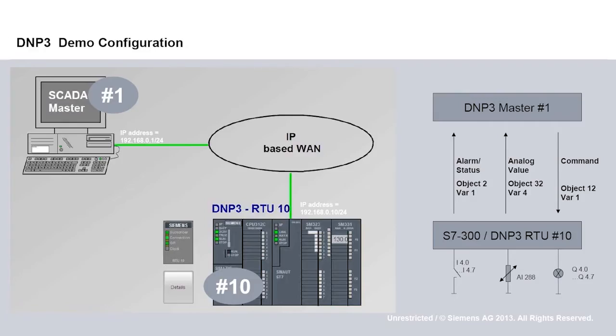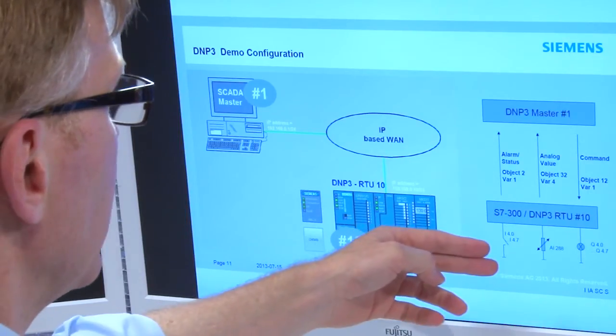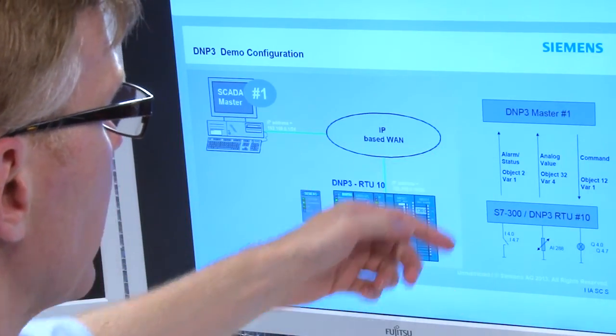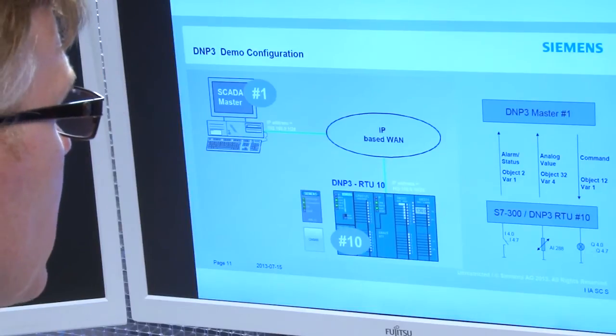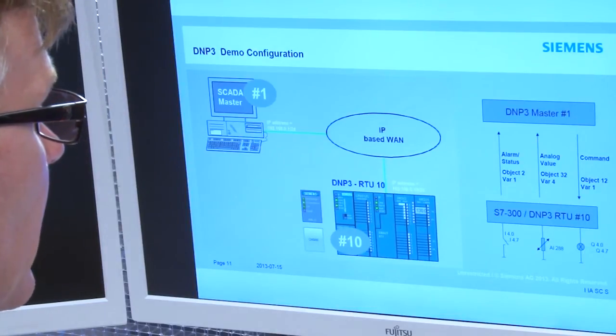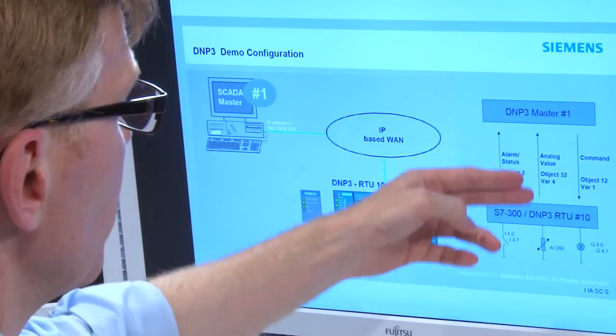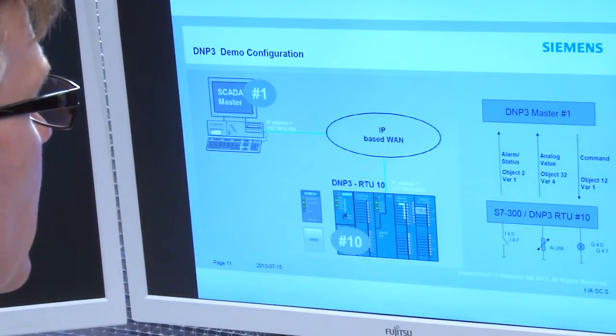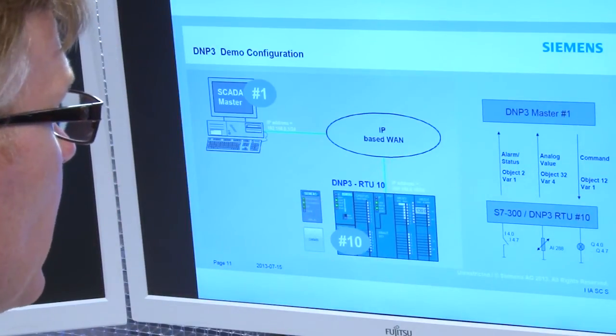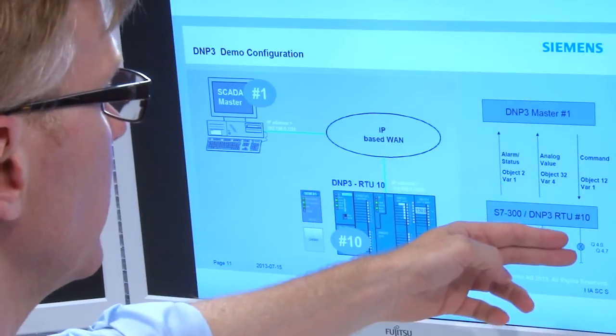The project is already available. It consists of a process station with DNP3 address 10 and a control system with DNP3 address 1. The binary values imported from the digital input are transmitted to the master as messages, as binary inputs Object 2. An analog value is gathered with the analog input module and transmitted to the master as DNP3 Object 32.